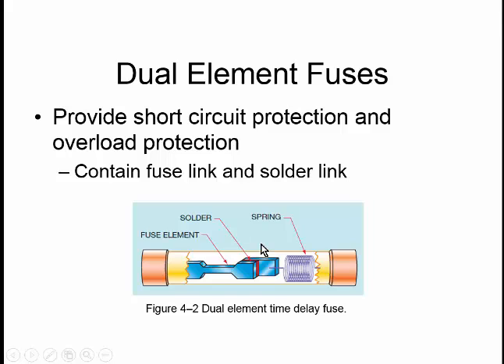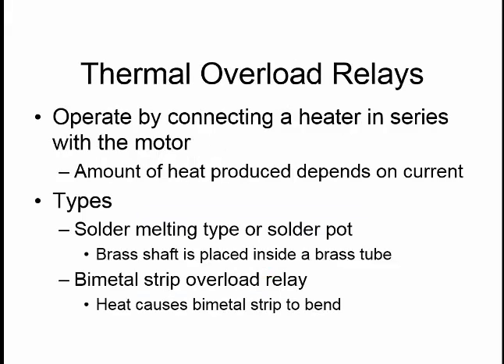So circuit breakers are short circuit protection. Fuses are normally short circuit protection. They're not overload protection per se for motor circuits, but you can get dual element fuses that provide overload protection. In a motor circuit, our fuses and circuit breakers are typically short circuit or ground fault protection, and typically overload protection is there for the longer, slower problems. Usually the problem is too much mechanical load attached to the shaft of the motor, which creates too much current flowing. If that persists for too long, you get heat, and if you get too much heat, you damage insulation. Incidentally, all electrical equipment is basically rated on heat. The warmer it gets, eventually the insulation dies. So it all comes back to heat.